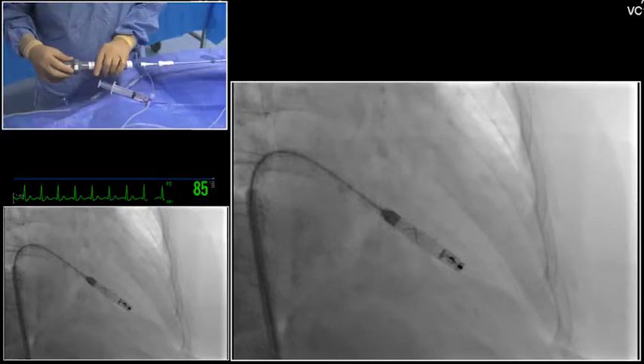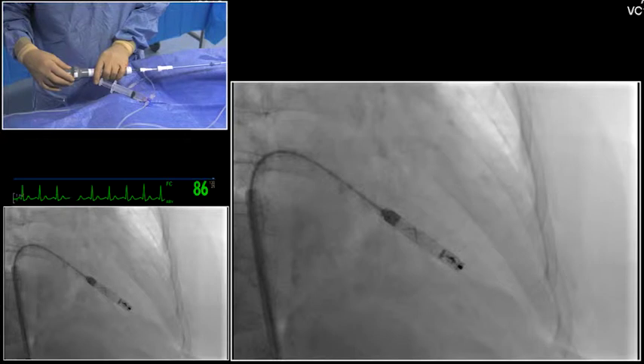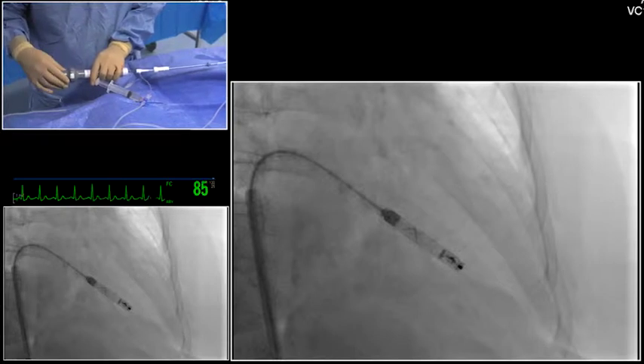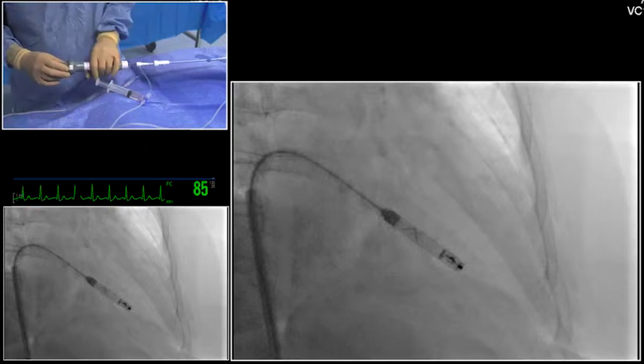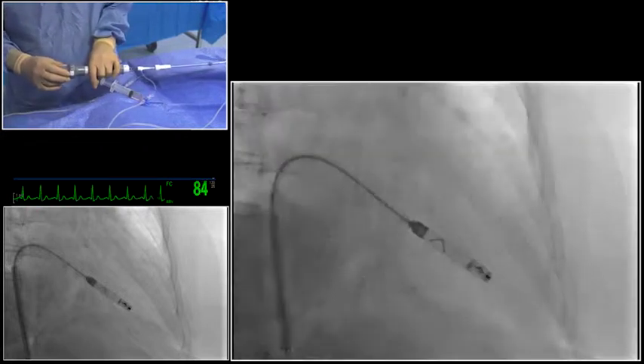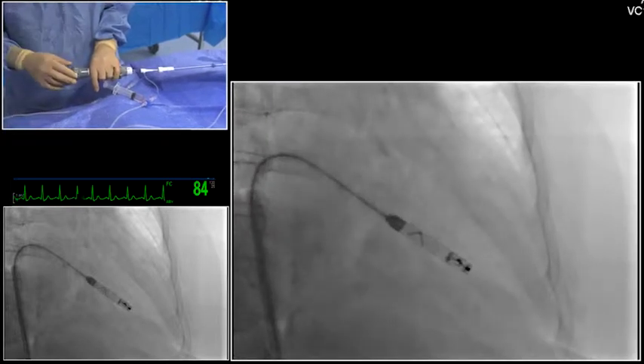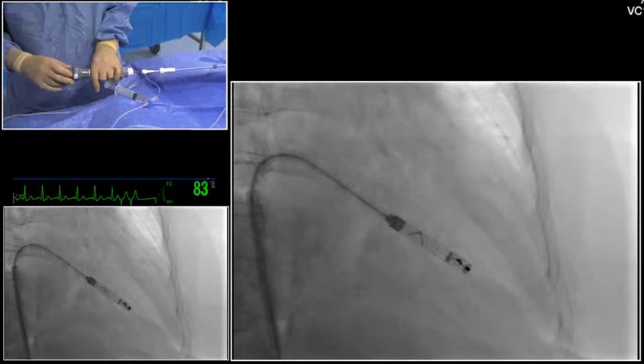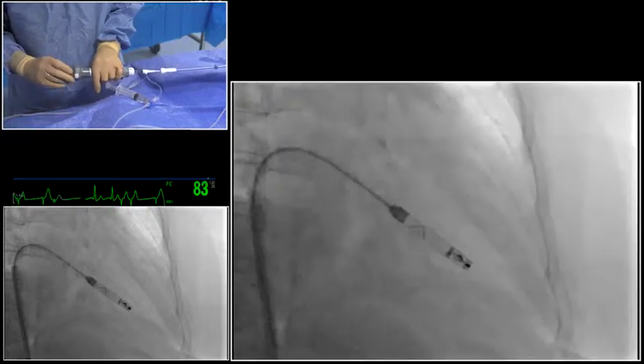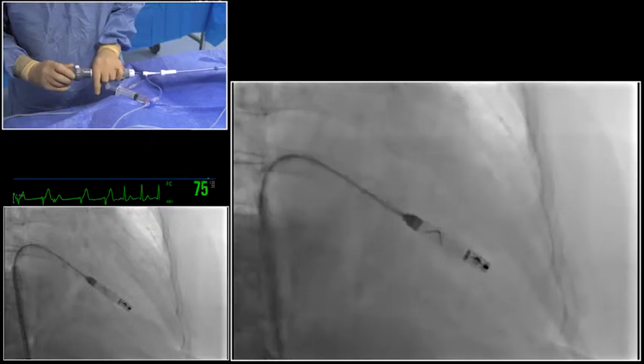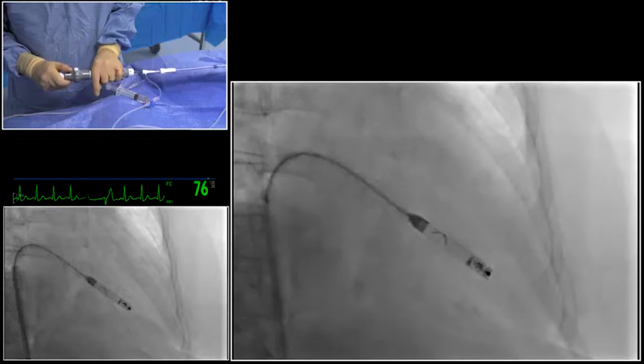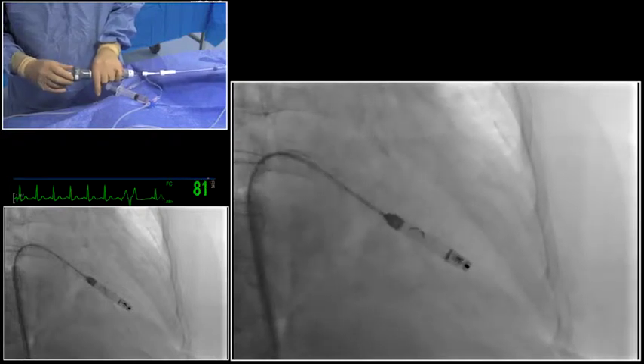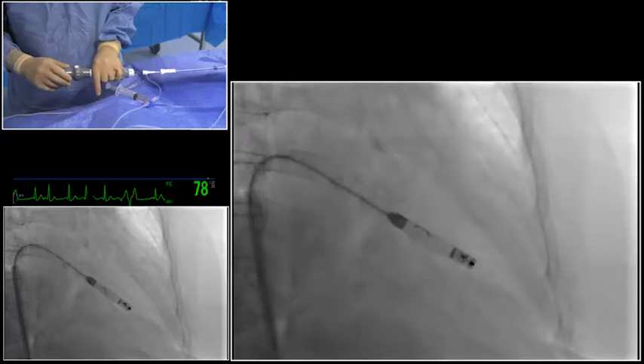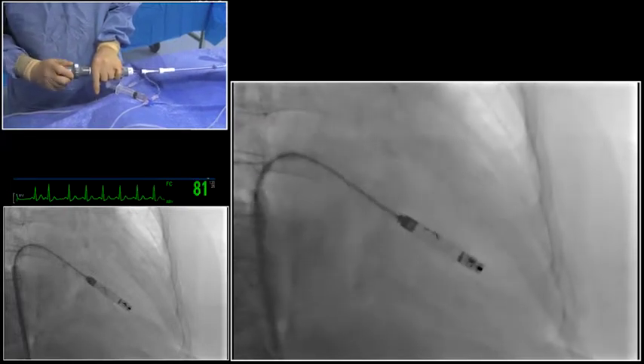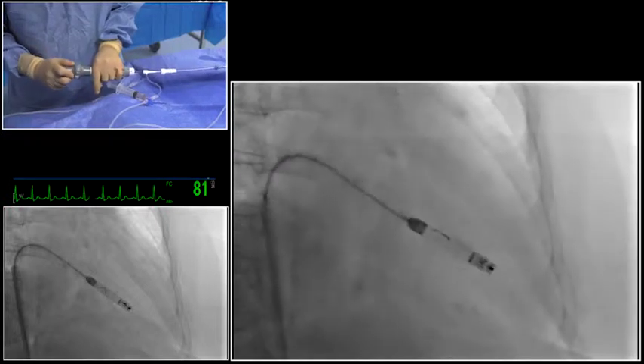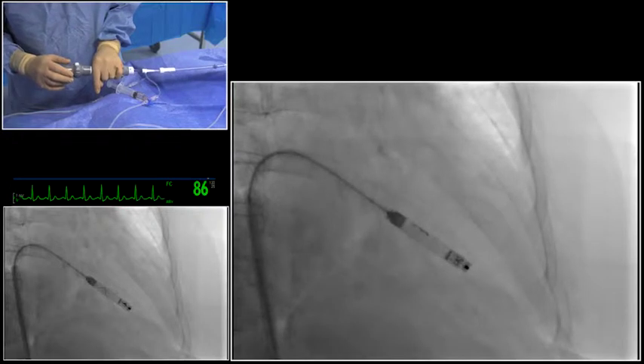So we will turn the handle to screw the nanostim, not too much, not at 20 clicks, generally between 10 and 15 clicks. And it has to be very slow, and under fluoroscopy. So we have a reference screen with a marker, and we have to do at least one turn. I will begin. Usually you have to do 4 or 5 clicks before you see that the device is moving. One quarter.